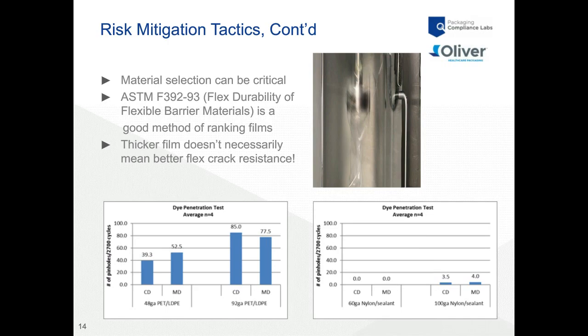You can see the twisting and turning that goes on—we're taking a film and twisting it. Typically the standard is 2,700 cycles. After that, we take a look at the film that's been tested and use dye to count the number of pinholes created. Not all materials are created equal in this type of test. Again, it's not necessarily a predictor of real world, but it's a great way to rank films to give you the best chance of surviving flex crack scenarios.